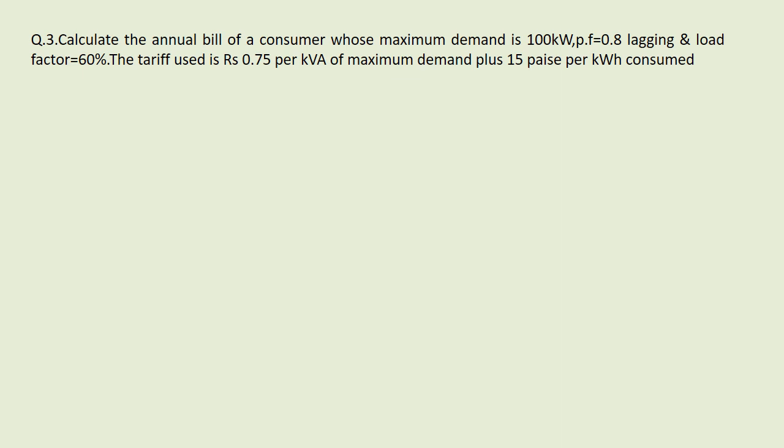Here, a point that was missing in the previous problem, question number 2, is that we did not mention the load factor. The load factor is mentioned here, so you should know that you need to calculate the average load. This tariff is based on two parts. One part depends on the kVA of the maximum demand, and the other part depends on kilowatt hour, and this kilowatt hour is not the maximum demand, it is the average load. So you need to calculate the average load first.